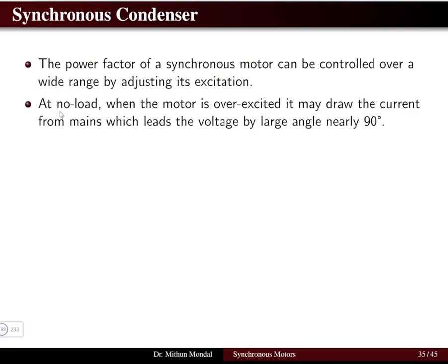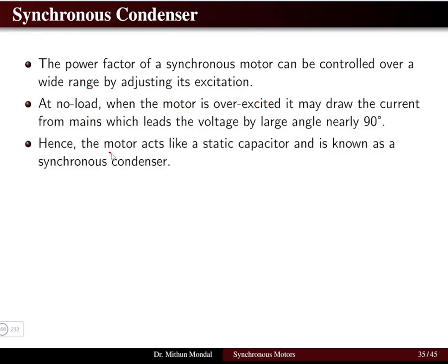Now what happens at the no load condition? When the synchronous motor is operating at no load condition, the motor is over excited. If the synchronous motor is at no load and over excited, then it may draw a current from the mains which leads the voltage by a very large angle, nearly 90 degrees. So it is basically a capacitive action. Now we can judge that the motor is acting like a static capacitor and is known as the synchronous condenser.